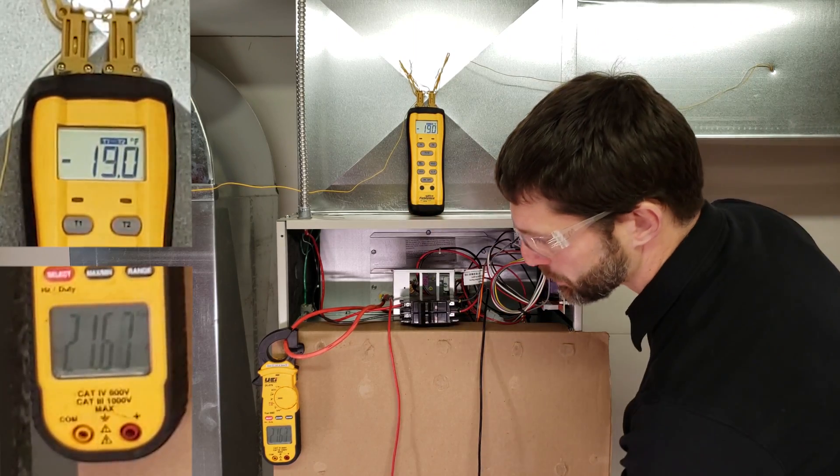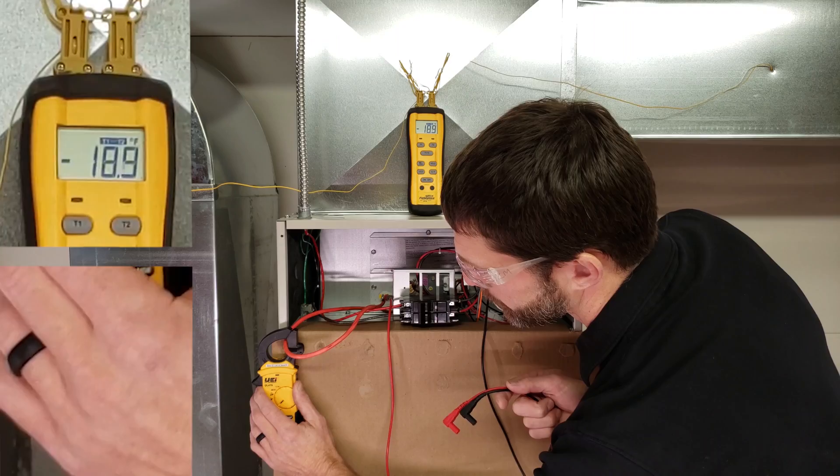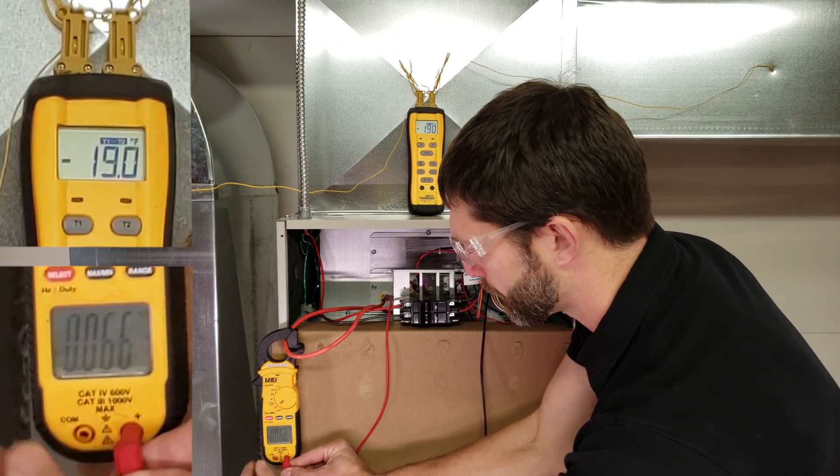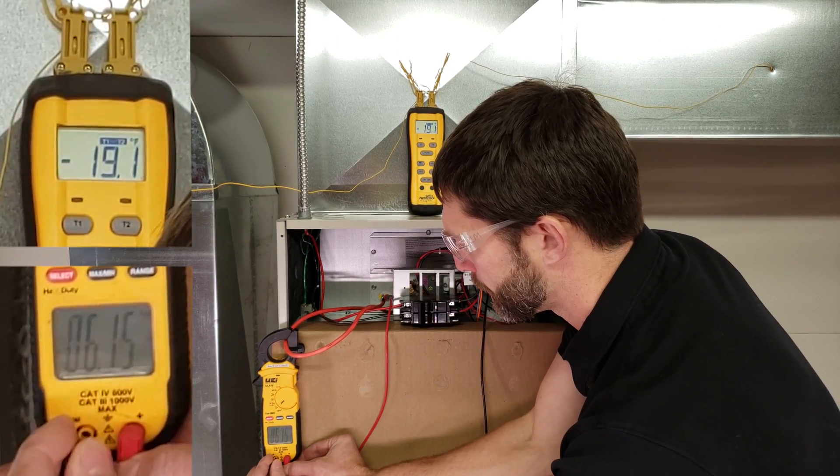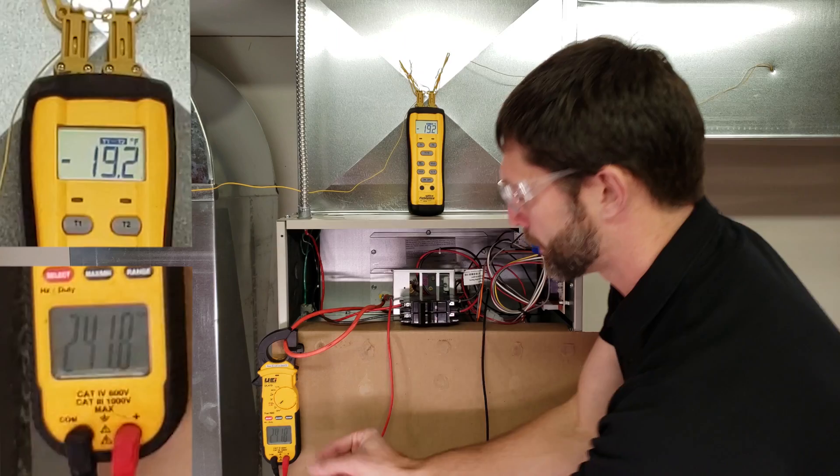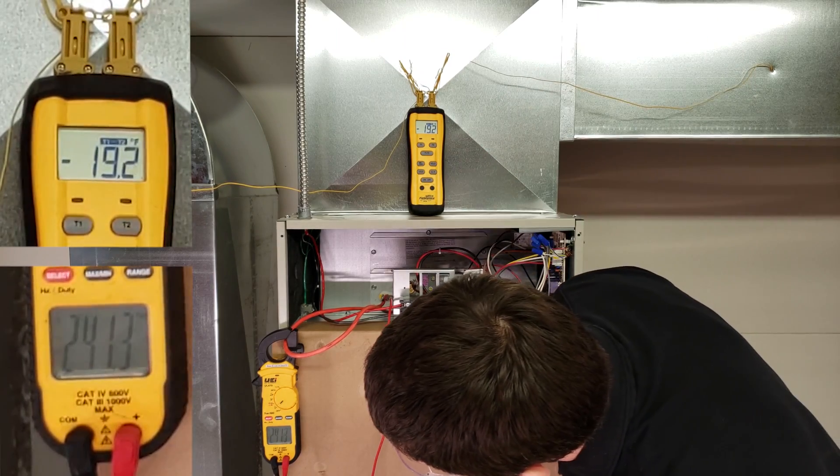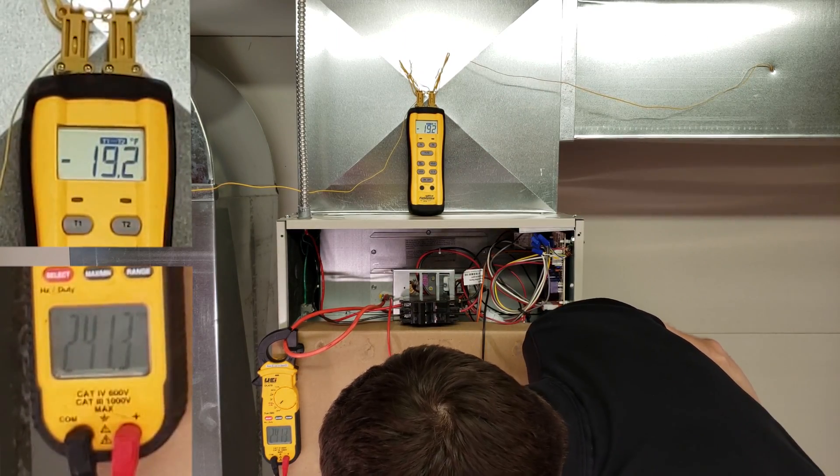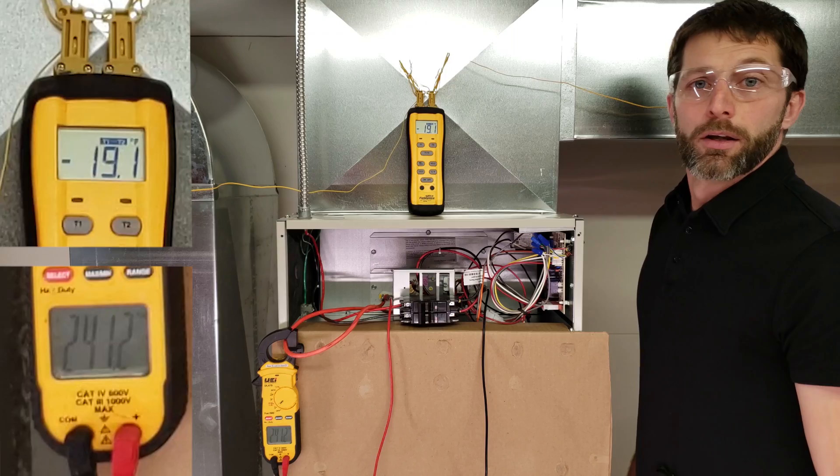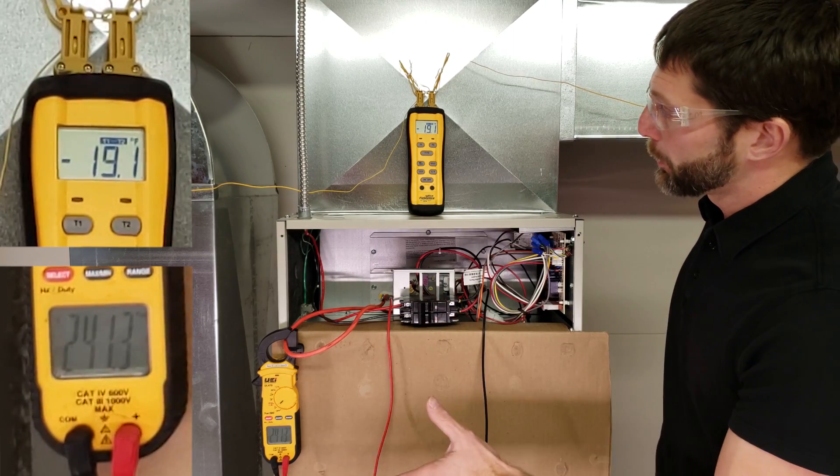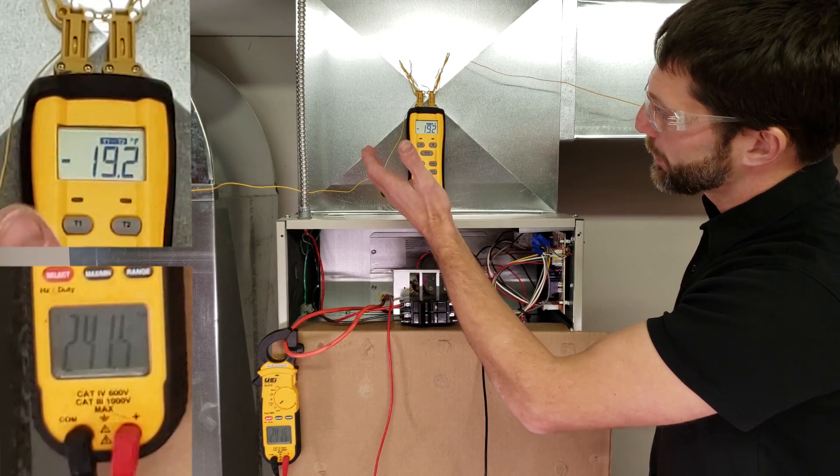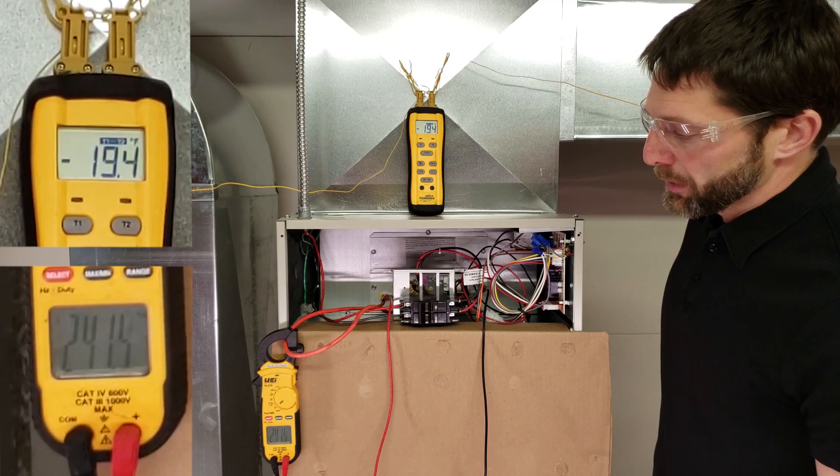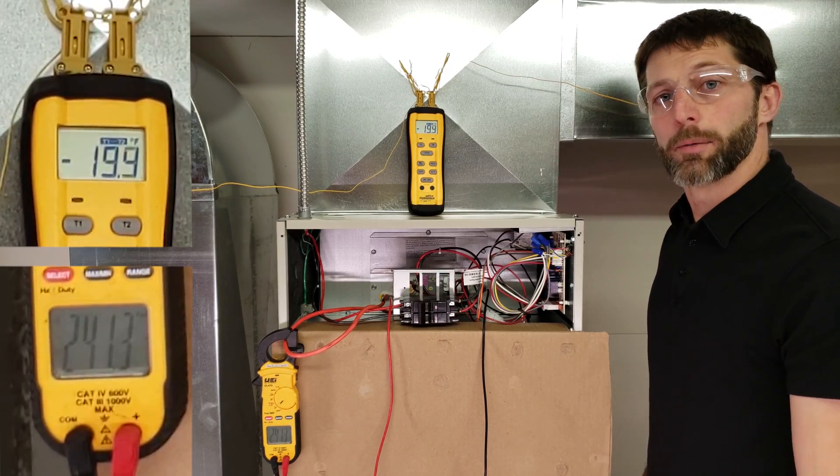And let's go ahead and check our voltage. And our voltage is 241.3. So we have our three measurements. This is right about 19.2 degrees. So we have our three measurements, and let's go ahead and input them into our formula.